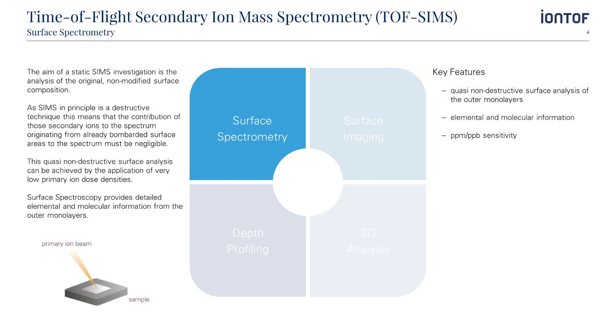The aim of a static SIMS investigation is the analysis of the original, non-modified surface composition. As SIMS is in principle a destructive technique, this means that the contribution of secondary ions originating from already bombarded surface areas to the spectrum must be negligible. This quasi non-destructive surface analysis can be achieved by applying a very low primary ion dose density. Surface spectrometry provides detailed elemental and molecular information from the outermost layers. The analysis consumes less than one percent of a monolayer, and you can achieve PPM or PPB sensitivity.